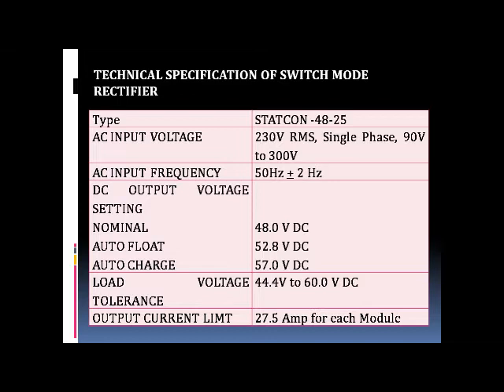Load voltage tolerance 44.4 volts to 60 volts DC. Output current limit 27.5 ampere for each module.